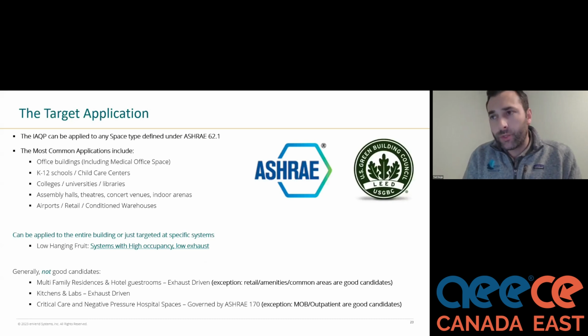Where's the IAQp most frequently applied? It's most frequently applied in office buildings, K through 12 schools, colleges and universities, pretty much anywhere where you're typically looking at low exhaust.